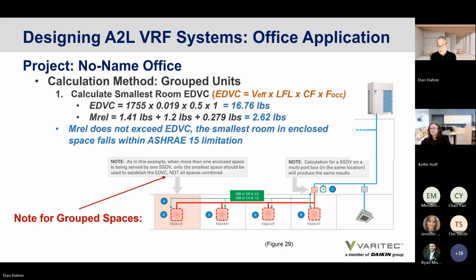Yeah, it is in addition to, you guys already touched on it a little bit, but the exempted spaces. It reads: areas that contain only continuous refrigerant pipe or tube, including joints and connections that have been tested in accordance with section 9.13, are exempt from the effective dispersal volume calculation unless these areas are part of connected spaces per 7.2.3.2. So I was just curious, with today's very thorough explanation rundown of the CAFs, thank you, Dan.